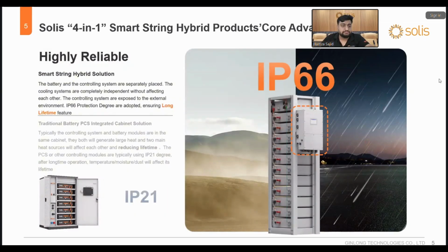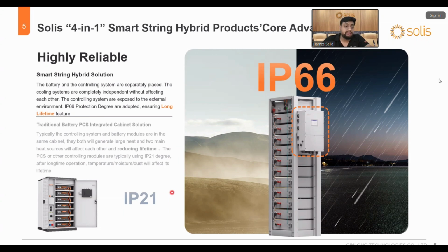So the next thing is highly reliable. Our inverter is IP66. So you can install any of the compatible batteries, okay? And you can install the inverter outside in a harsh environment and it can still work. But if you compare with the traditional battery PCS integrated solution, the battery and the inverters, like PCS and all the other components, are installed in an IP21 cabinet, which is not good for the health of the system. Why? Because both systems produce heat, which is not good for the life of the system, because two things are continuously creating a lot of heat, and due to IP21, temperature, moisture, and dust will affect its lifetime.